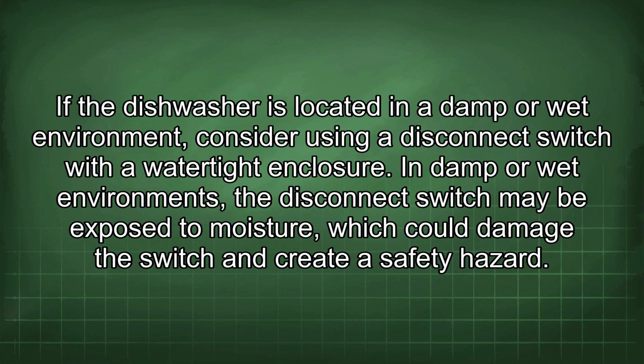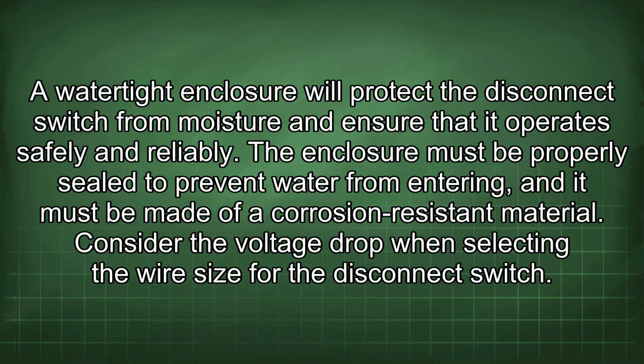In damp or wet environments, the disconnect switch may be exposed to moisture, which could damage the switch and create a safety hazard. A watertight enclosure will protect the disconnect switch from moisture and ensure that it operates safely and reliably. The enclosure must be properly sealed to prevent water from entering, and it must be made of a corrosion-resistant material.